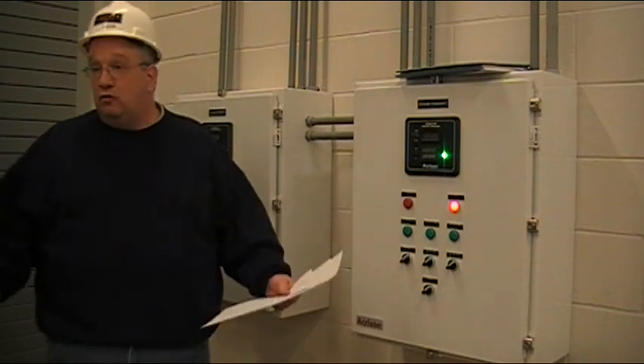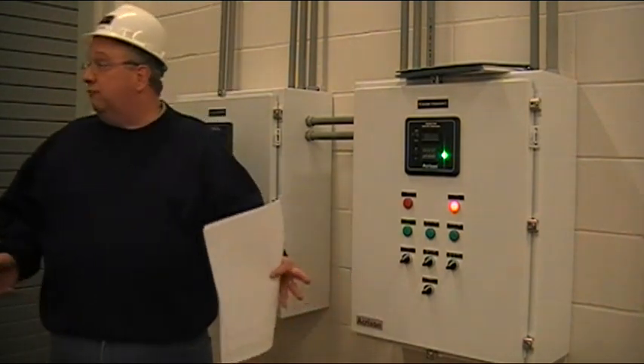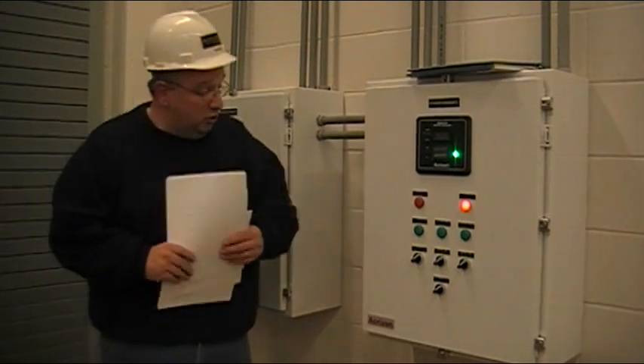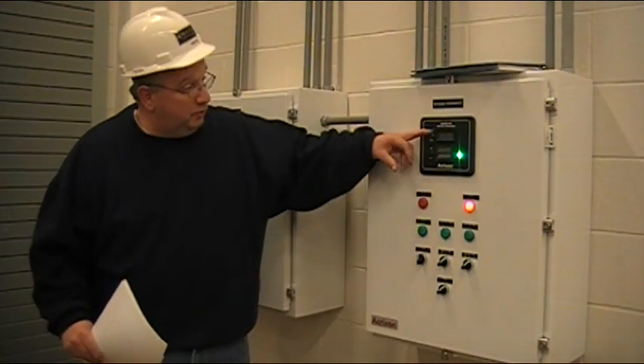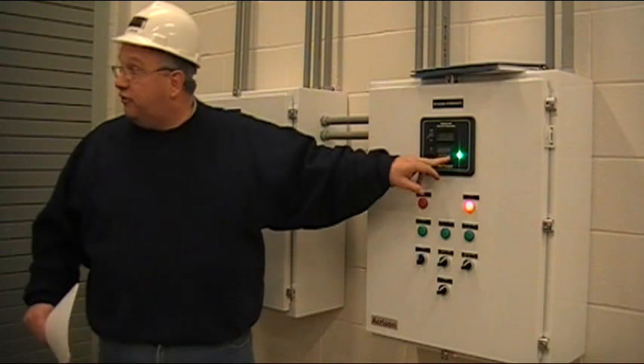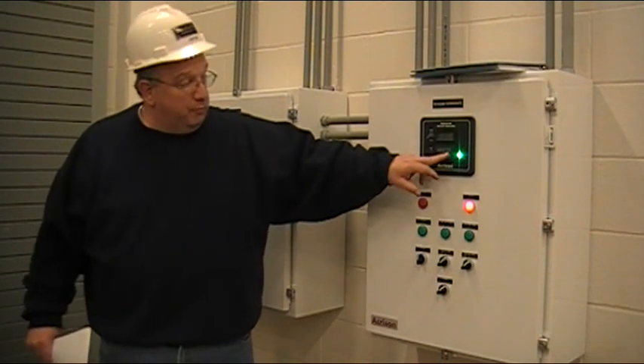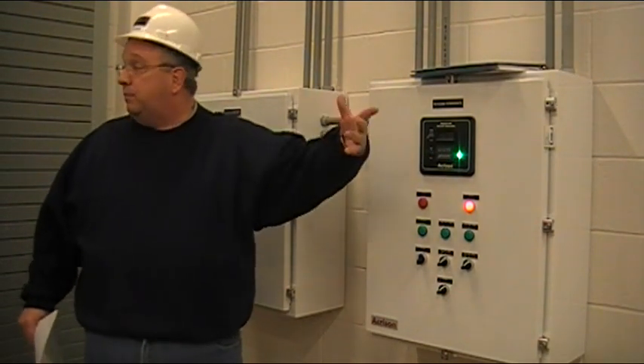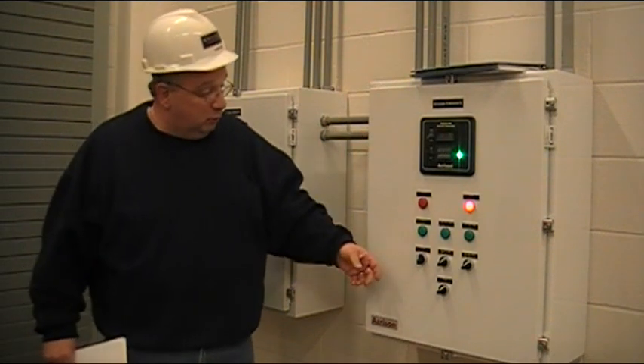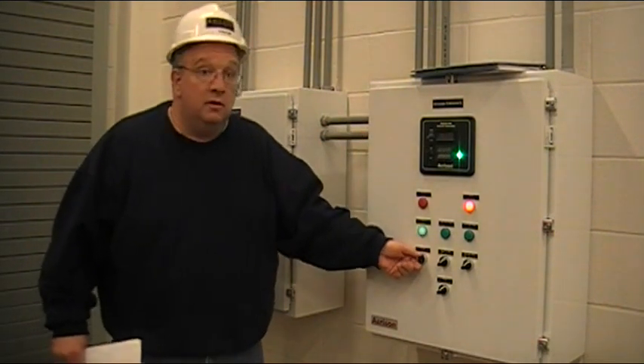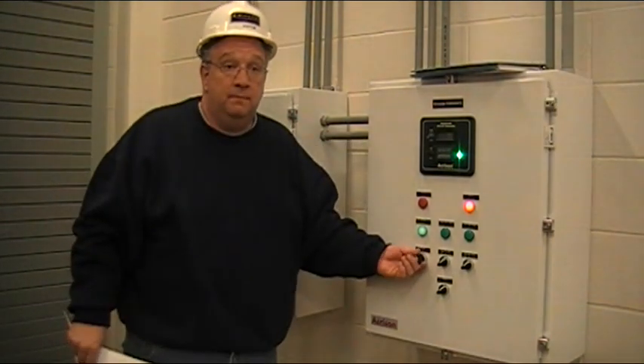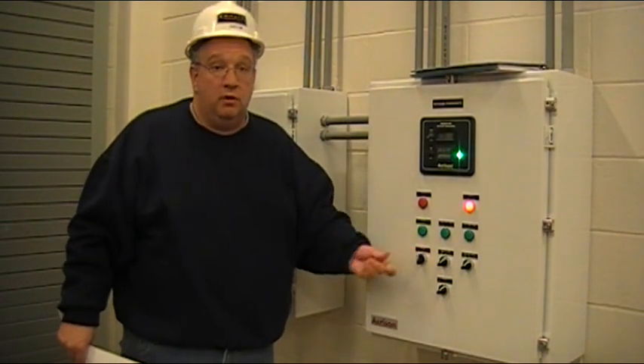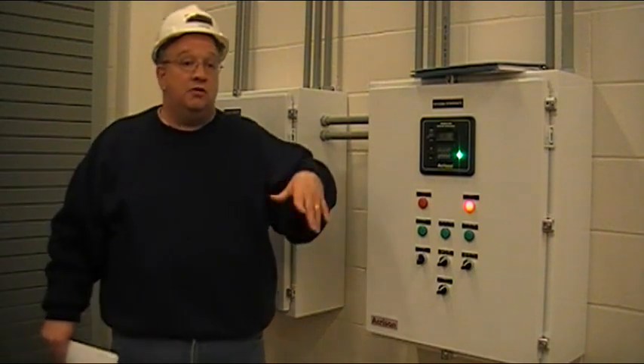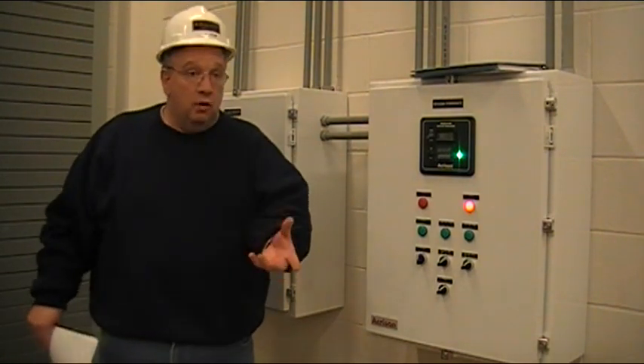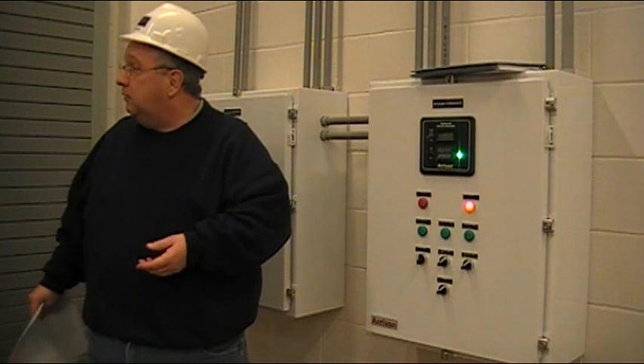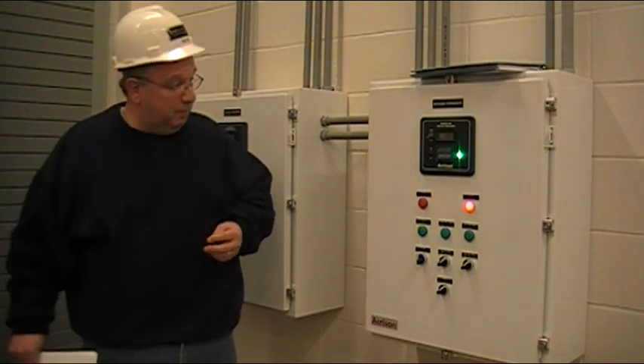Well, how would you do that? Well, you're not going to want to run it in auto and have water, so what you would do is put this in hand, and then you would run off the thumb wheel over here. 100% means you would run the motor at 100% motor speed, 99.9. So when we run this, you can actually see the feeder running now. And we don't want to do that for too long, so what you would do is get your bucket underneath there, start running it, and time it out as best you can to get your sample.